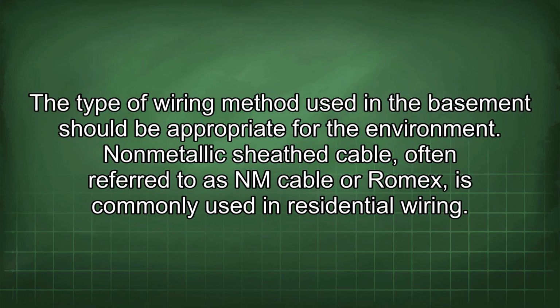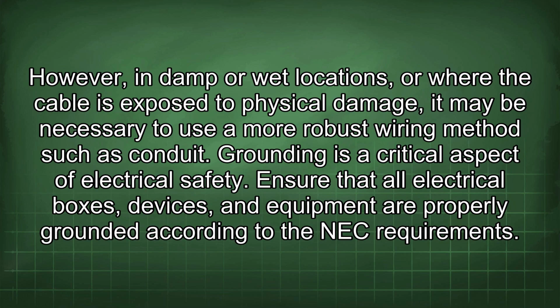The type of wiring method used in the basement should be appropriate for the environment. Non-metallic sheath cable, often referred to as NM cable or Romex, is commonly used in residential wiring. However, in damp or wet locations, or where the cable is exposed to physical damage, it may be necessary to use a more robust wiring method such as conduit. Grounding is a critical aspect of electrical safety. Ensure that all electrical boxes, devices, and equipment are properly grounded according to the NEC requirements.